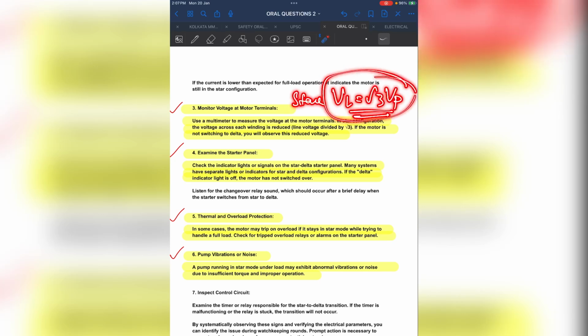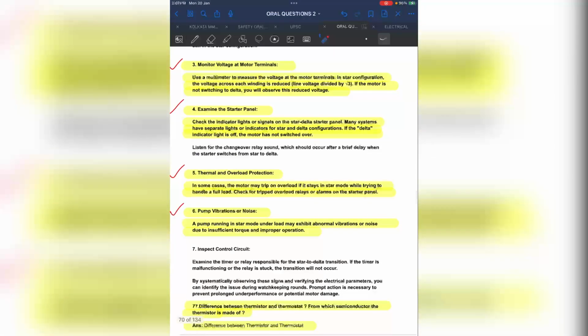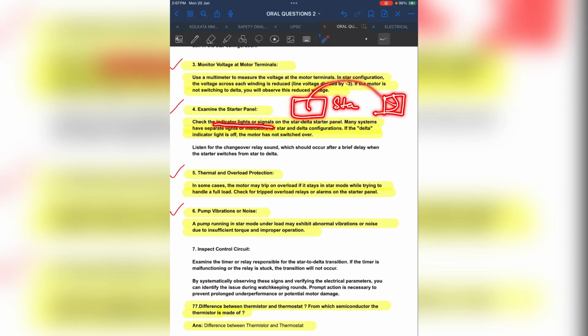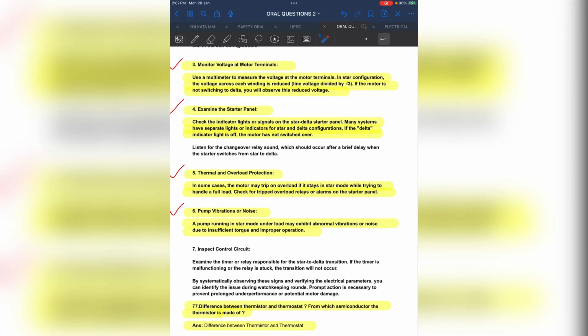You can check the motor current also, and your voltage will also reduce in the star configuration, as I already told. And you also know that in delta our line voltage is equal to phase voltage, but in our star connection, our line voltage is √3 times the phase voltage. So you also know from here our voltage is reduced. You can also examine the starter panel and check the indicator lights, because some starter panels have a star and delta indication lamp. If there is a switch over, then there must be an indication from star to delta. You can observe the indication at the starter panel.